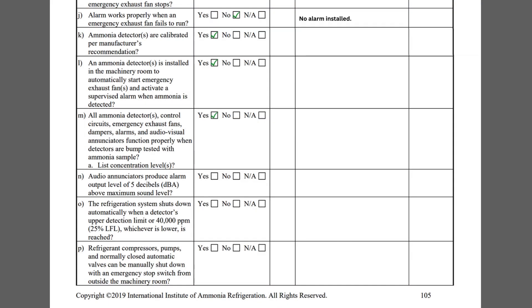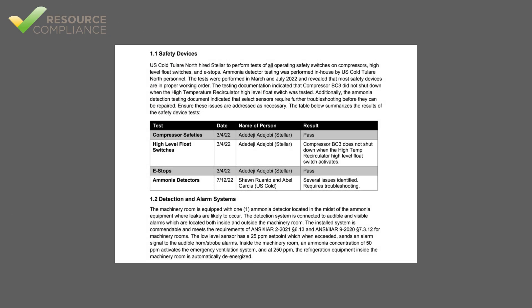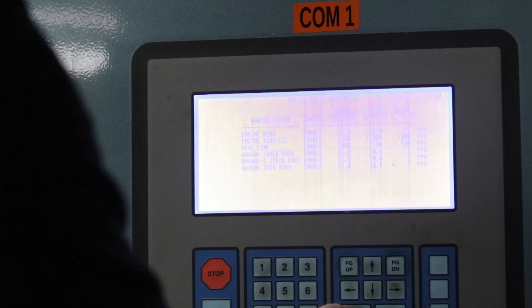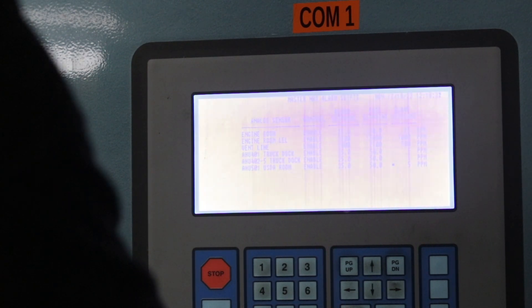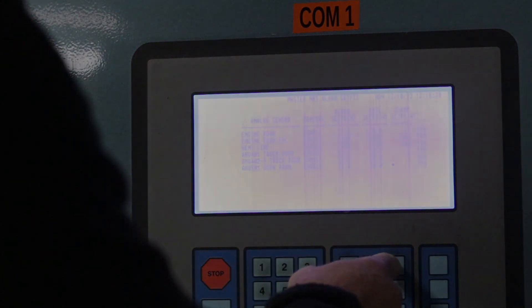Item M asks if all of the ammonia detectors, control circuits, emergency exhaust fans, dampers, alarms, and audiovisual annunciators function properly when detectors are bump tested with an ammonia sample. Additionally, Subpoint A requests that the ammonia concentration levels be listed. Ideally, the facility will have a functional description of the ammonia detection system listing all set points. The set points can also be verified at the PLC HMI.